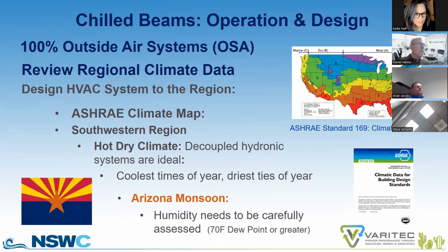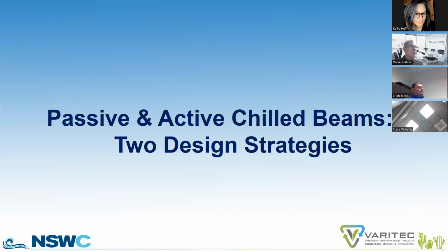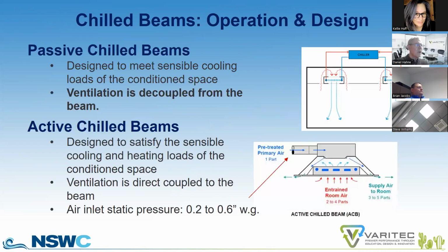Arizona is perfect for chill beam systems, but we do need to be sensitive to our Arizona monsoon. I just registered a month ago a dew point outdoors of 72 degrees. Fortunately, we don't see that for days and weeks on end. In fact, it'll even fluctuate within a 24-hour period of the day. But if you lose dew point control in a building, you can start creating some architectural and HVAC systems with condensation building up and adding to all sorts of problems to an environment. So what are passive and active chill beams? What are their design strategies? How do they work? What are some of the considerations?